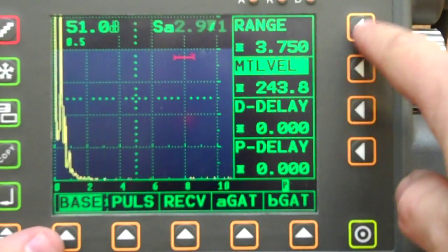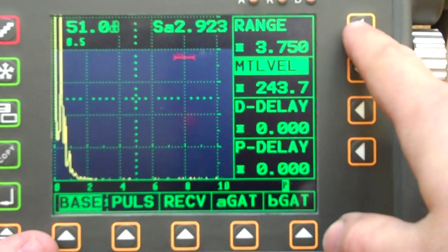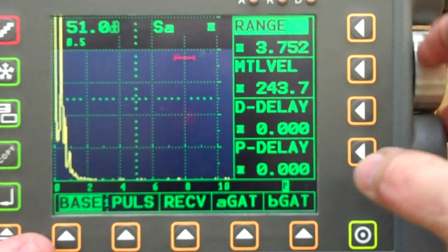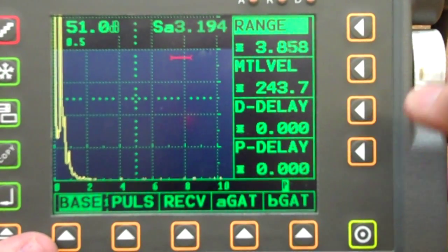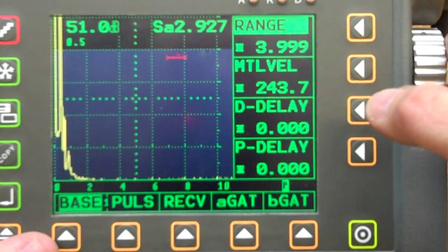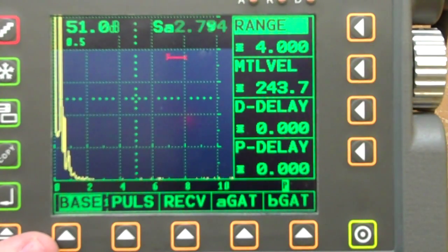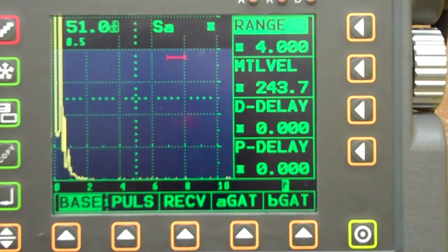So we would go back to our base menu. Let's say we're going to set a 4-inch range, like Lab 2 says. There's our 4-inch range. Place the back wall echo at 80% using the dB control.